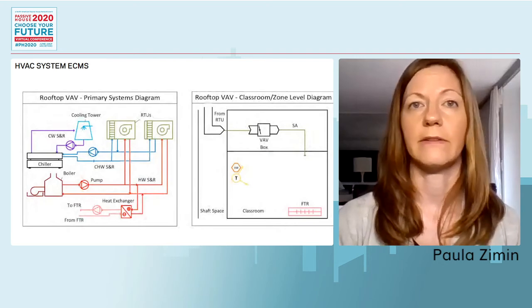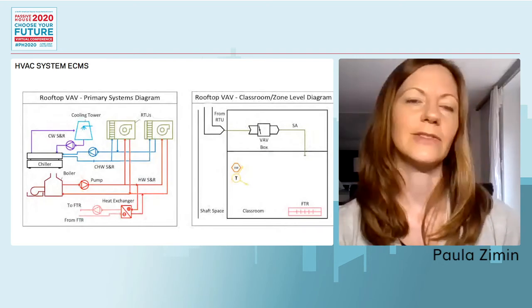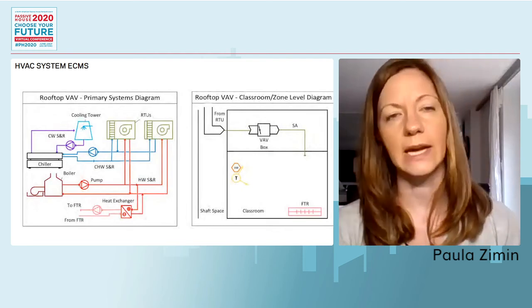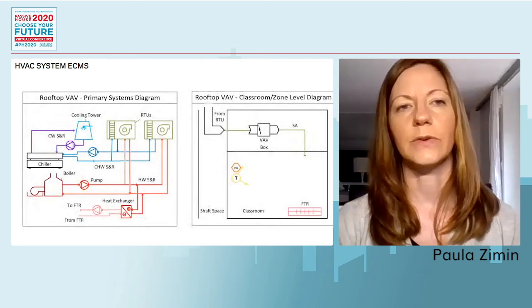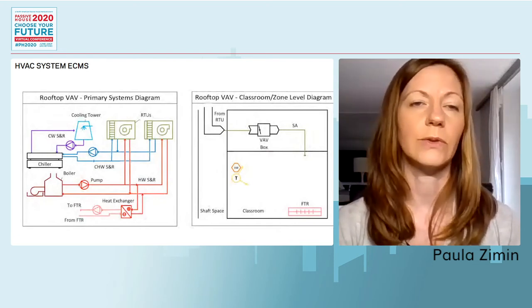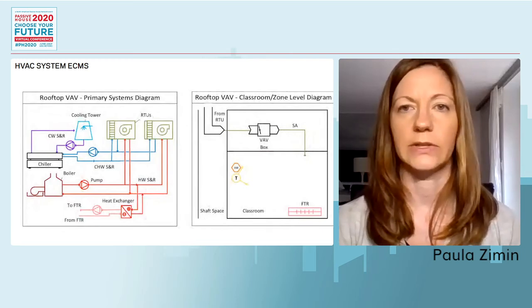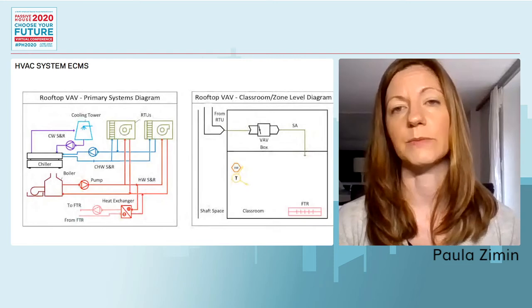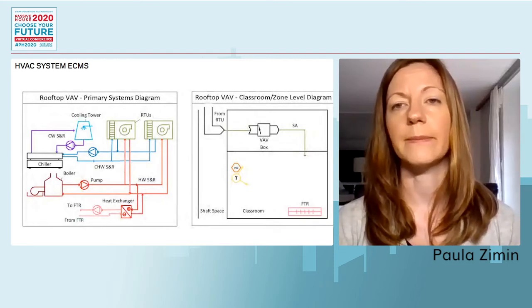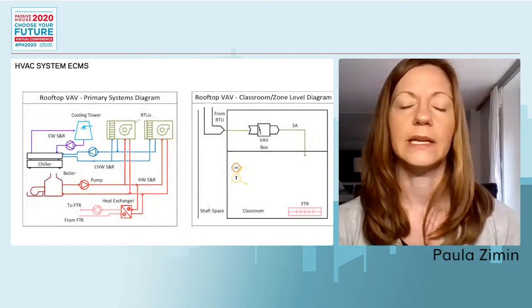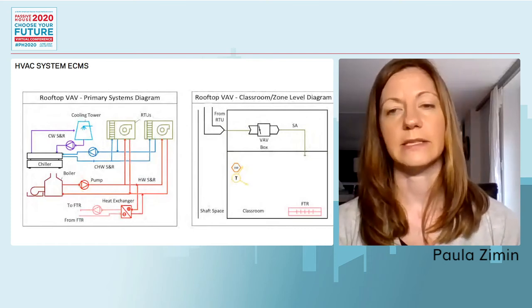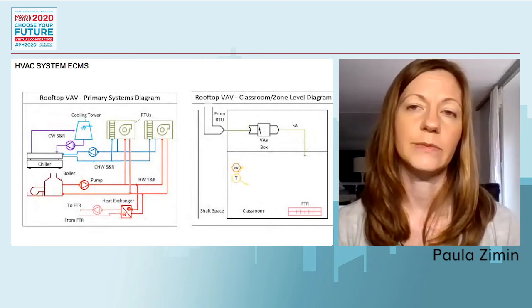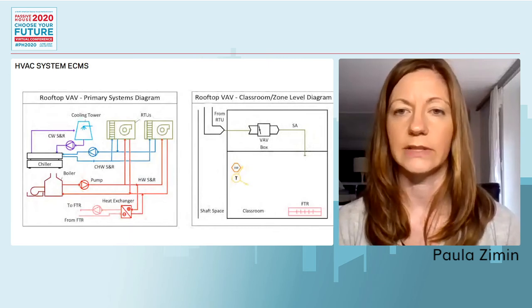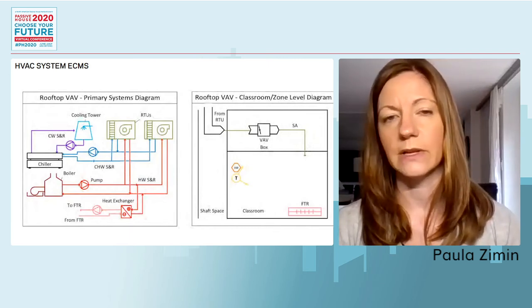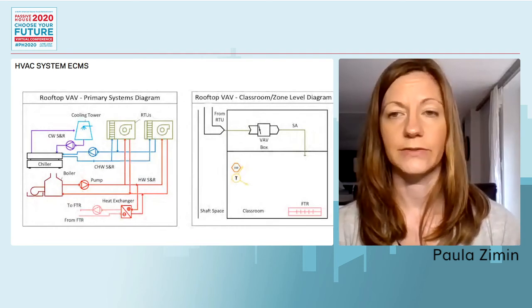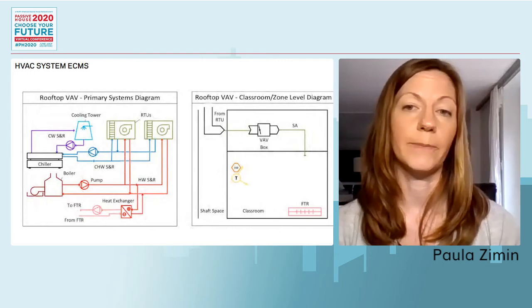The cooling tower has a benefit in that it increases the efficiency of the cooling system, but then there are other operational issues with the cooling tower and issues related to Legionnaire's disease. So there were a couple of iterations of this system with and without the cooling tower, with modular chillers and modular boilers, etc. And so that's how the water systems move. And then the air moves primarily ventilation air, and cooling is provided through the RTUs to VAV boxes in classrooms. And there are occupancy sensors in the classrooms, which will vary the amount of outdoor air delivered to a classroom. And then those fin tube radiators are providing the heat for the classroom along the exterior perimeter wall.